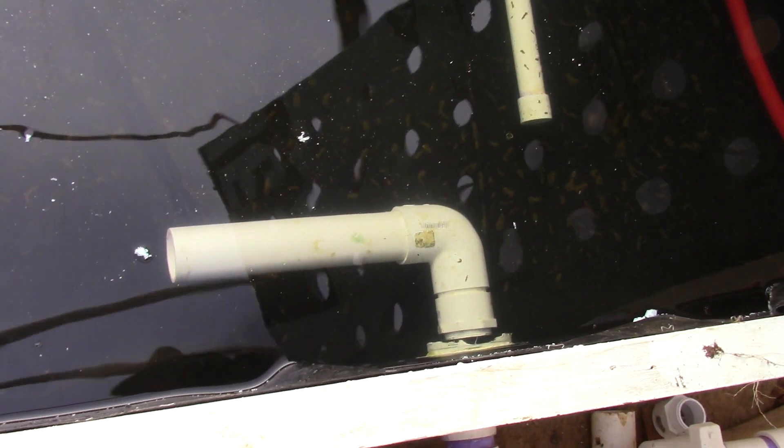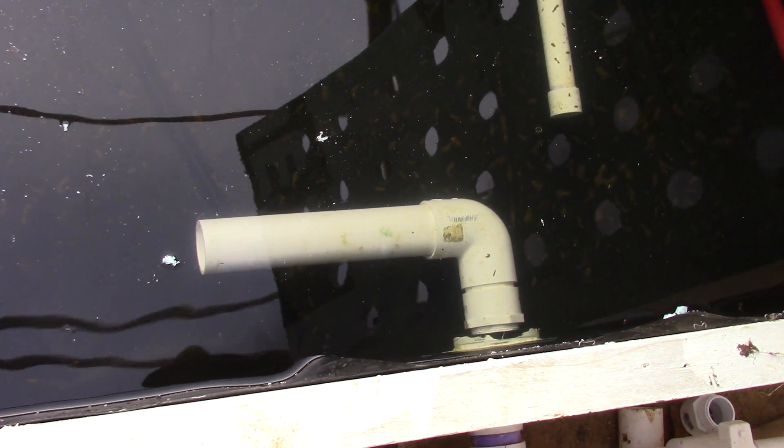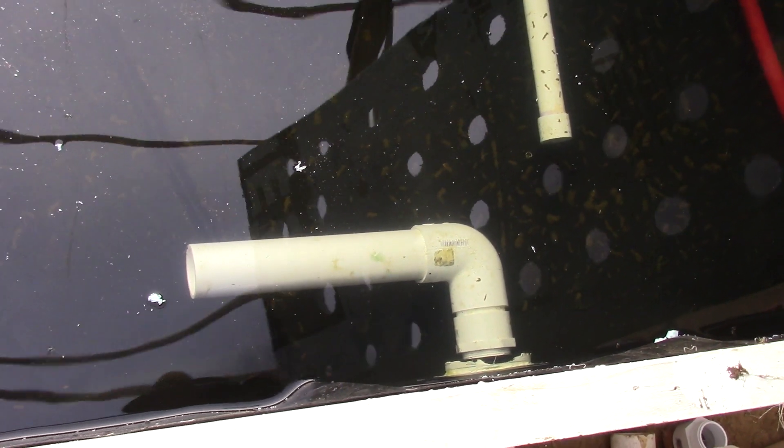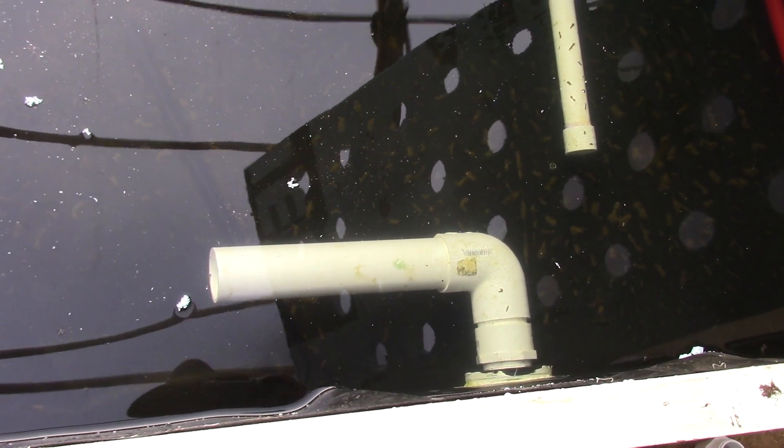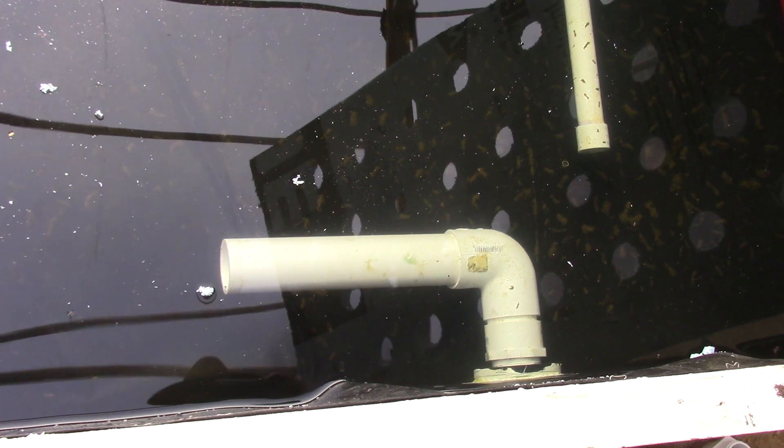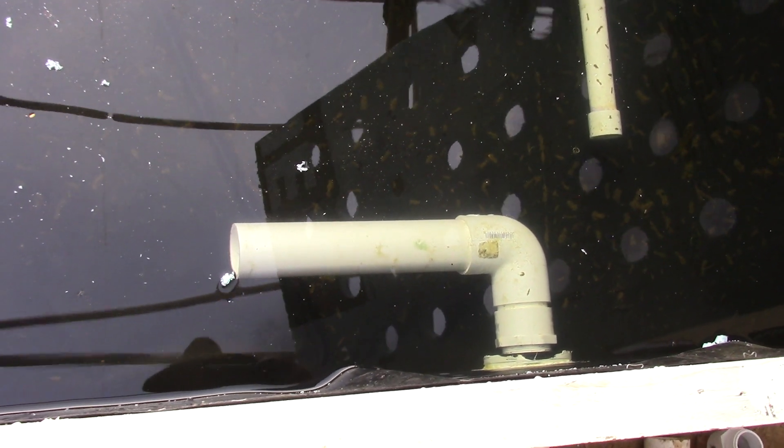I raised that inlet pipe just as high as I could without getting a whirlpool in it. I did have a filter on it. It was stopping up and causing the pump to cavitate and I couldn't have that, so I took it off.